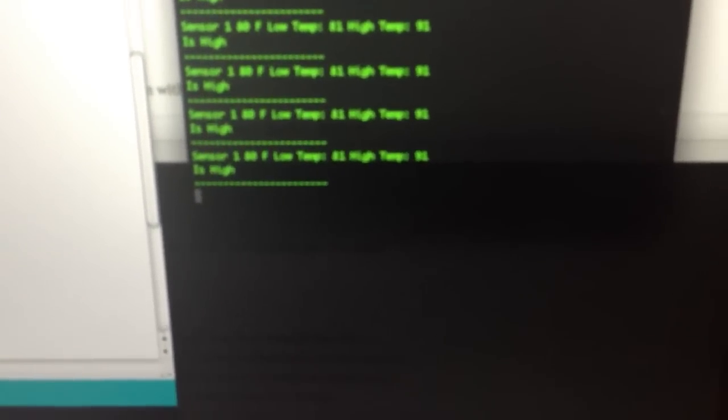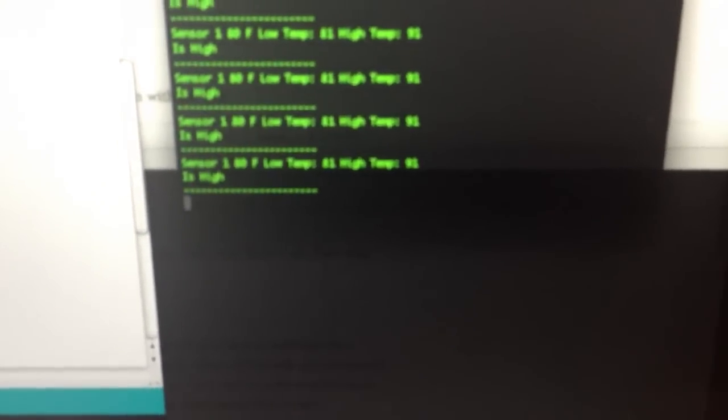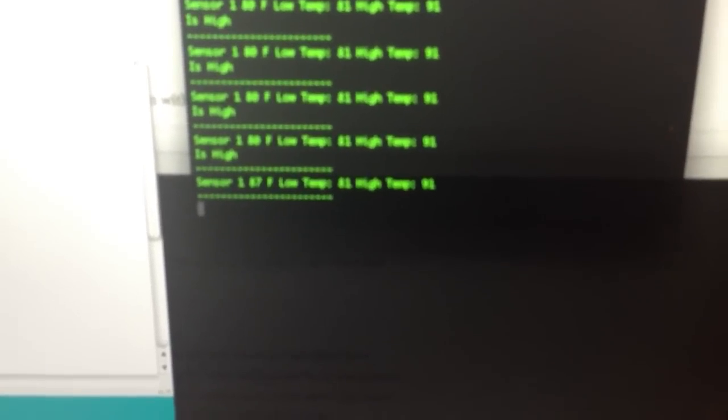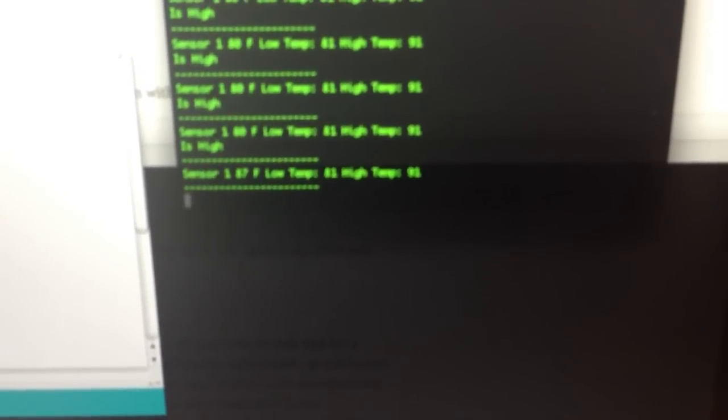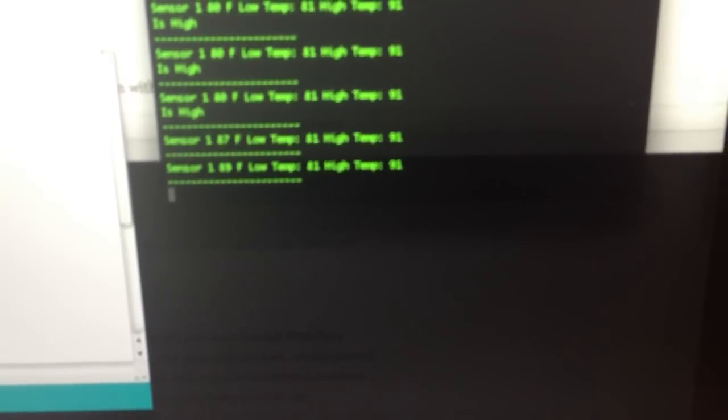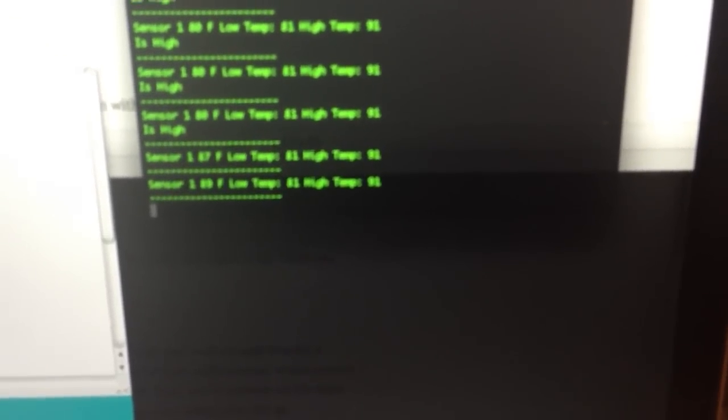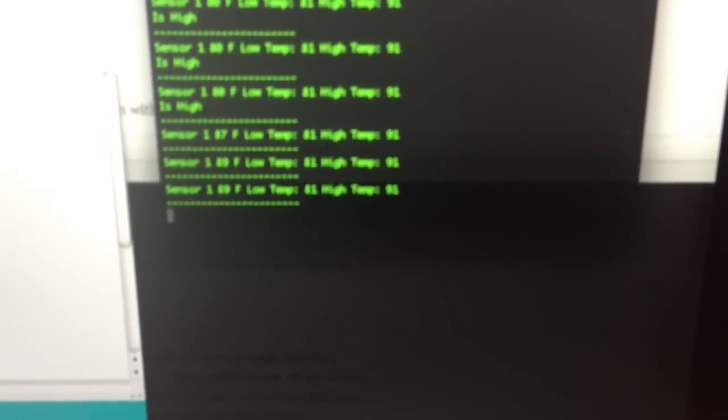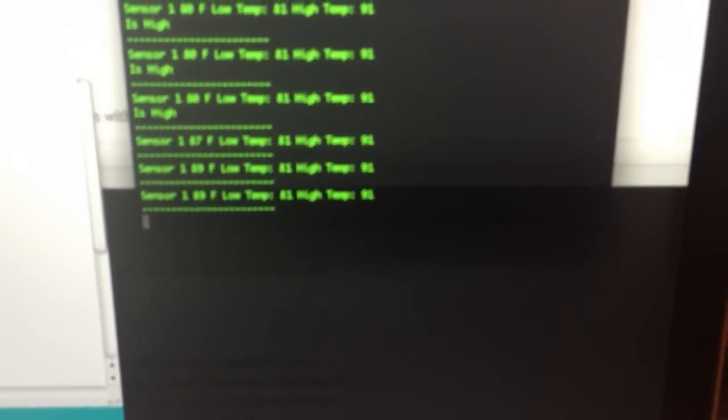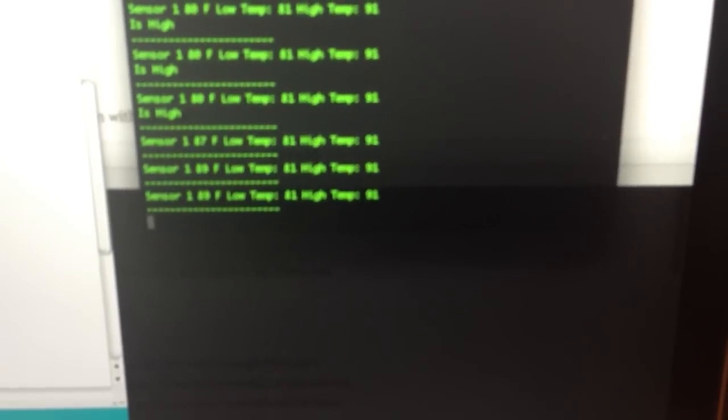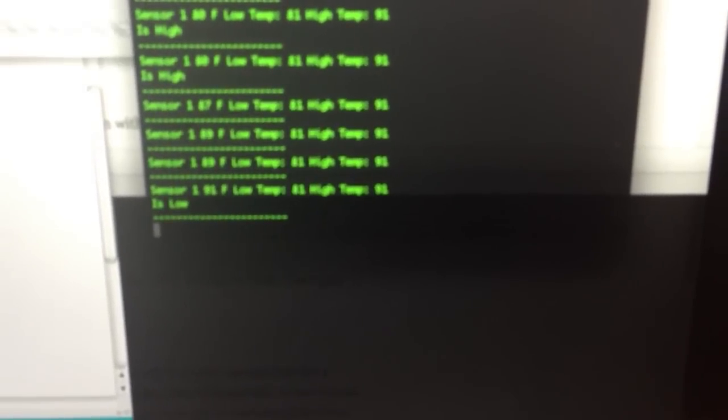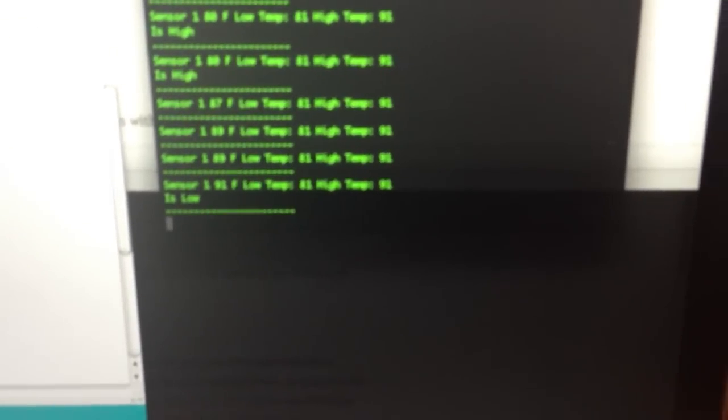You can see sensor one is currently at 80 degrees, low temp is 81, high temp is 91, hence the reason why this board is on. But if I take my finger and I pinch the sensor, it should start to heat up here. There it goes - 87. I'm just taking samples every minute. 89, 91. It'll shut the sensor off. There, it says is low, you can see the sensor shut off.